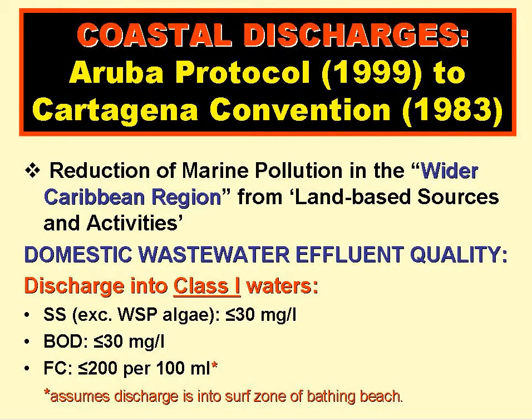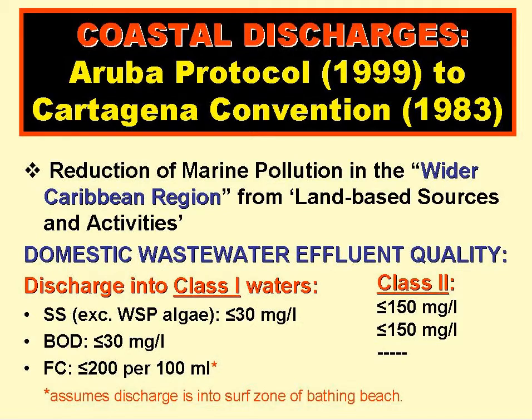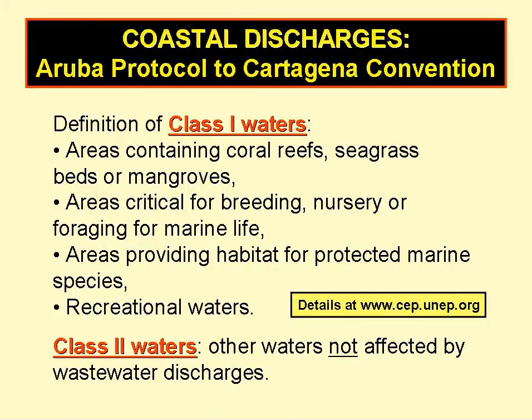Good examples of standards for coastal discharge are in the Aruba Protocol of the Cartagena Convention, which is basically a treaty signed by all states in and around the Caribbean. The Aruba Protocol seeks to reduce marine pollution from land-based activities, which basically means wastewater discharges to the sea. For discharges into class 1 waters — which are sensitive waters — the BOD and suspended solids both have to be no more than 30 milligrams per litre, and the faecal coliform count in the surf zone just off beaches has to be less than 200 per 100 ml. For discharge into class 2 waters, the only requirements are that the BOD and suspended solids both have to be no more than 150 milligrams per litre. Class 2 waters are essentially not affected by wastewater discharges.